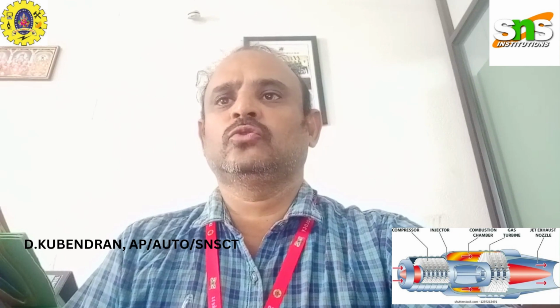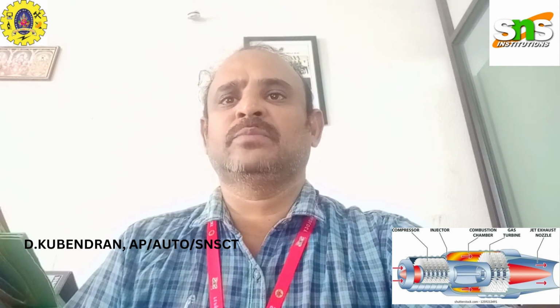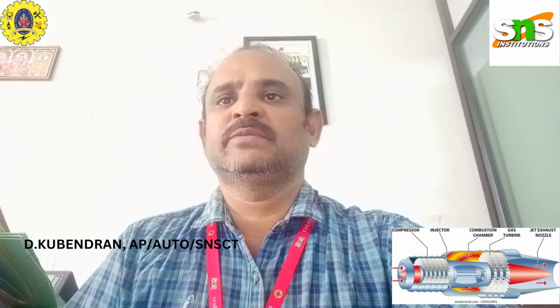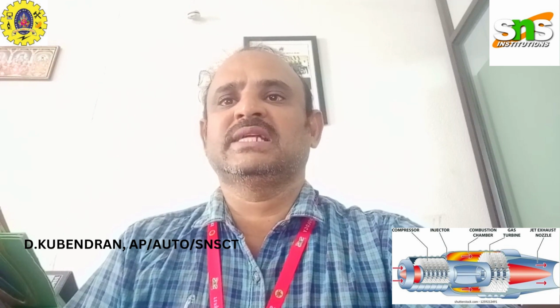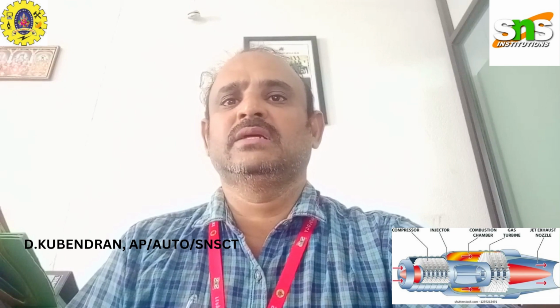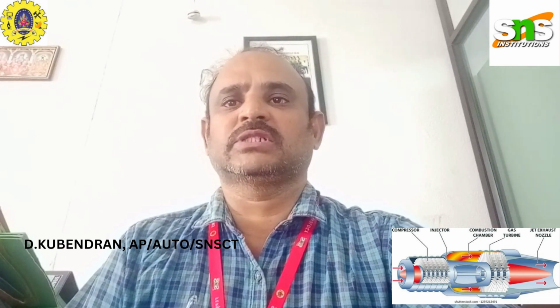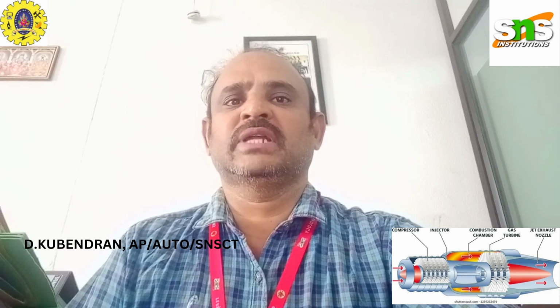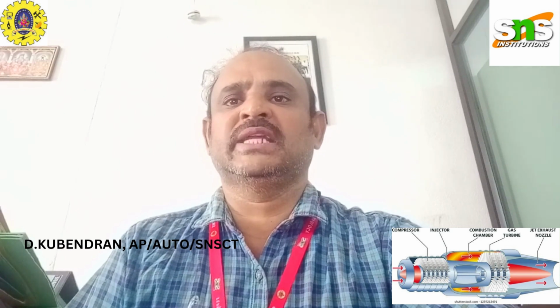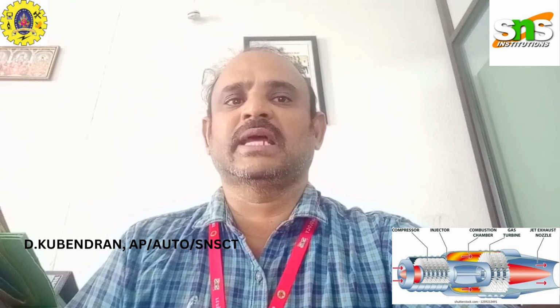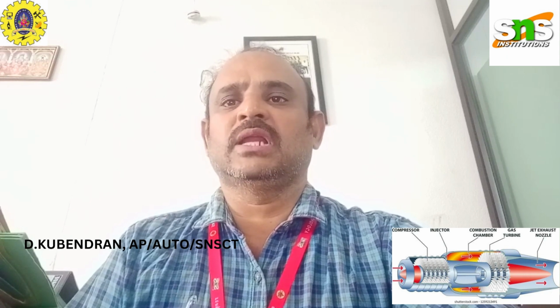Atmospheric air flows through the compressor that brings it to higher pressure. Energy is then added by spraying fuel into the air and igniting it so that the combustion generates a high temperature flow. This high temperature pressurized gas enters a turbine, producing a shaft work output in the process, used to drive the compressor. The unused energy comes out in the exhaust gases that can be repurposed for external work, such as directly producing thrust in a turbojet engine or a rotating second independent turbine that can be connected to a fan, propeller or electrical generator.